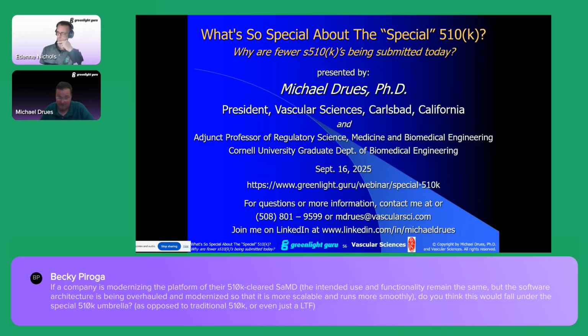If you can't convince them of that, then I think you're probably going to be looking at a special 510K. But two last things to remember, Becky. One is, at least in my view, whether you're doing a special 510K or a letter to file, the work that you're doing, in your case the validation, the V&V, showing that your changes in architecture are not going to impact safety, efficacy, performance, and so on.